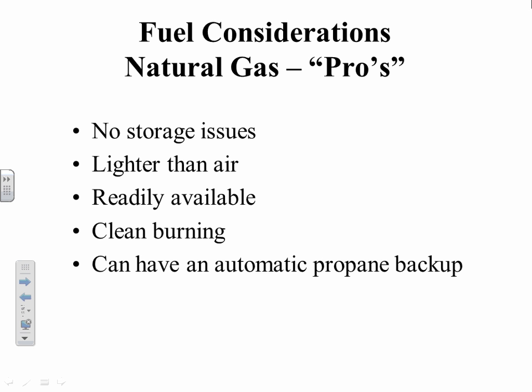And engineers discovered a long time ago in an earthquake, you can rupture a natural gas line. And for an emergency generator, that's a bad thing. So they said, well, let's have an automatic propane backup. And we can actually switch these on the fly. So if there's ever a rupture, there's sensors that say, okay, shut the solenoid valve off for natural gas, turn on the propane, open that valve, and away it goes. It takes off again. Sometimes it can do it on the fly, sometimes it just restarts. So that's the automatic propane backup.